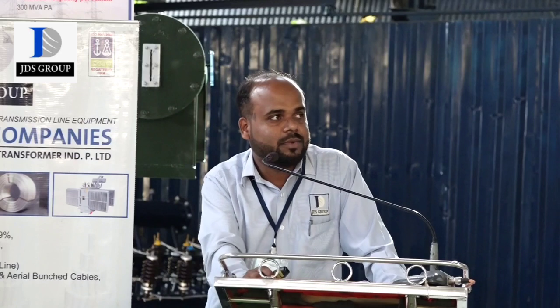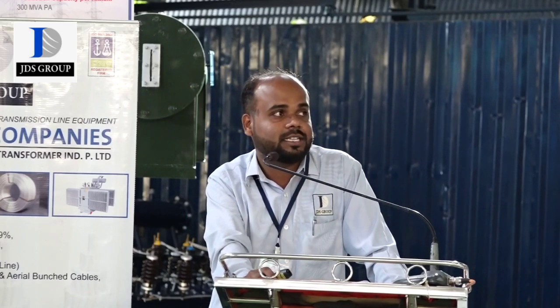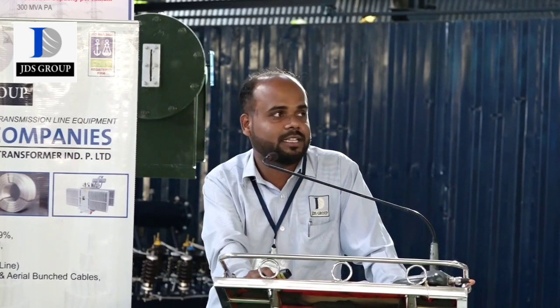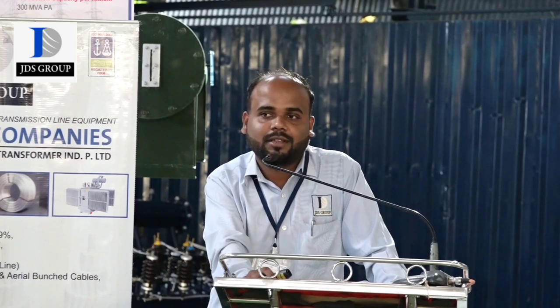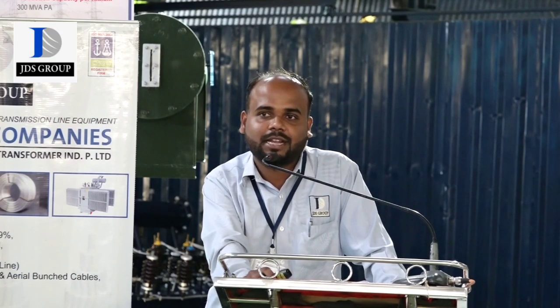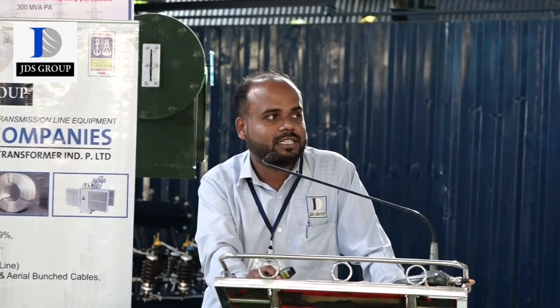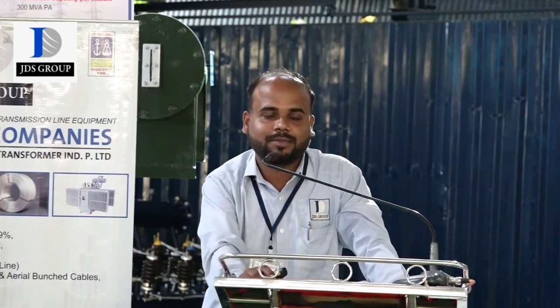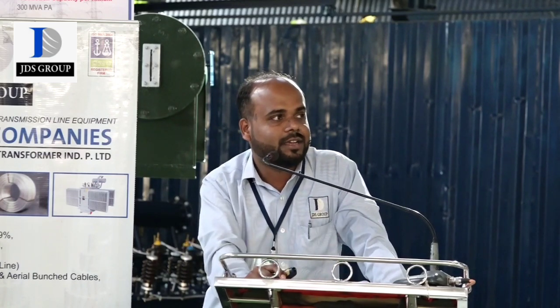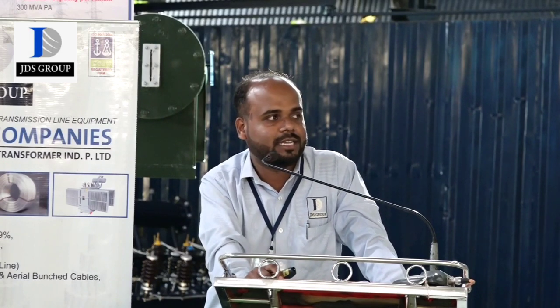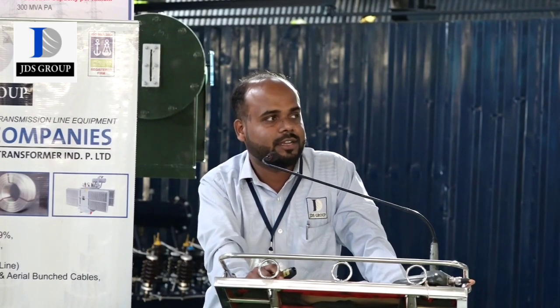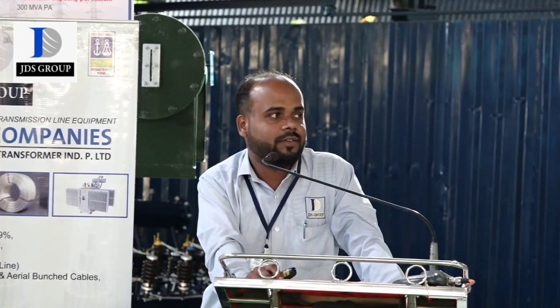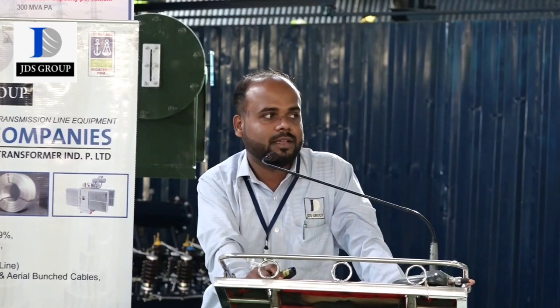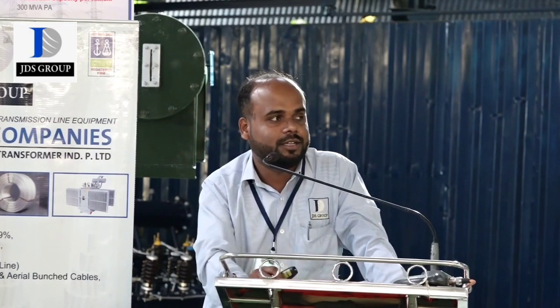The second stage is the insulation resistance test, which is the most important test for the transformer. Before energizing the transformer, we check its moisture, because if moisture is present in the transformer, it will be destroyed and will not run successfully. The insulation resistance test is done with an instrument called a Megger. For the active winding, we take the insulation resistance in three formats: HV winding to earth, LV winding to earth, and HV winding to LV winding. The minimum recommended value on the Megger is 2000 megaohms for a distribution transformer.